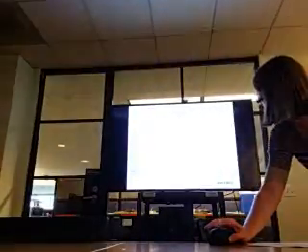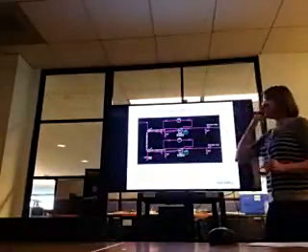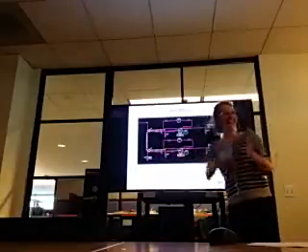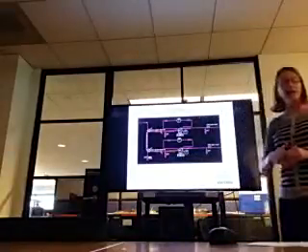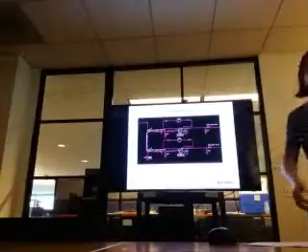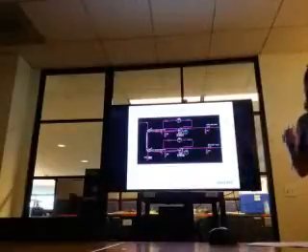So now let's say the engineer decided that they marked the P&ID like this, and they wanted to change the 3-inch to 2-inch. Is there anything else that needs to change? There you go. So right, the butterfly valve here needs to go to a ball valve. So that's where that tool would come into play. But you could also look elsewhere on the P&ID. Also, if you were to go to this material spec, you're not going to see a butterfly valve in the 2-inch size. So that's where you have to remember what you're doing.